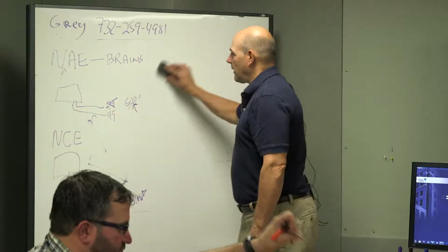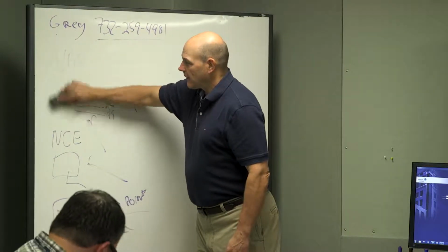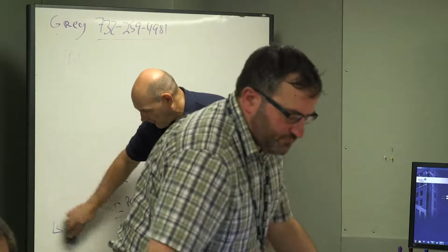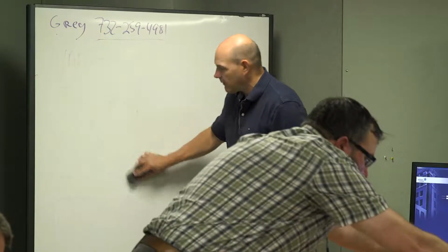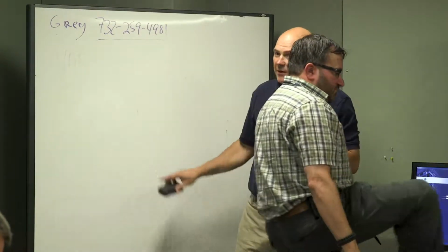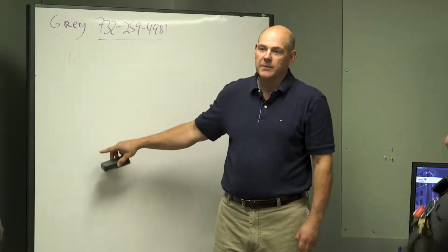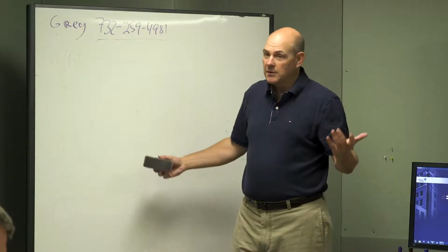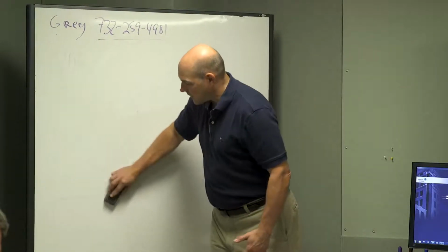And I always start there because everyone panics when the whole screen is blank, when it could just be one controller. When you go to the controllers, and when we have Nick on board, he'll explain to you the lights on each one of them. Is it communicating? Is it working correctly? They do have fault lights on them.